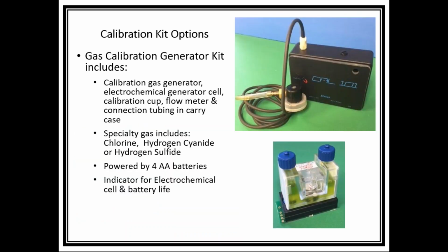The third calibration kit option that we have is the gas calibration generator kit. This is actually a very unique device that allows you to make your own calibration gas, very specific flow rate, very specific calibration. It's a one-shot type of operation. In other words, when you buy your calibration electrochemical cell, you have to specify the speed that you want, the flow rate that you want, and also the concentration. This cell is then plugged into the bottom of the unit, and it immediately starts flowing gas through your tubing and to your detector.